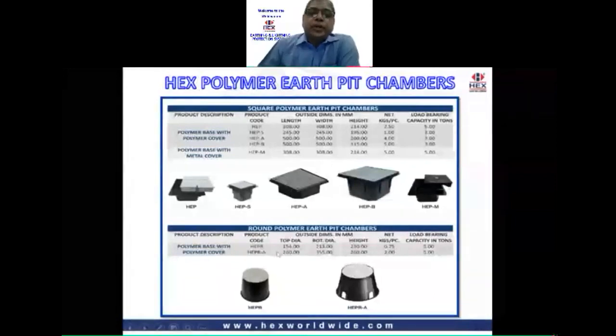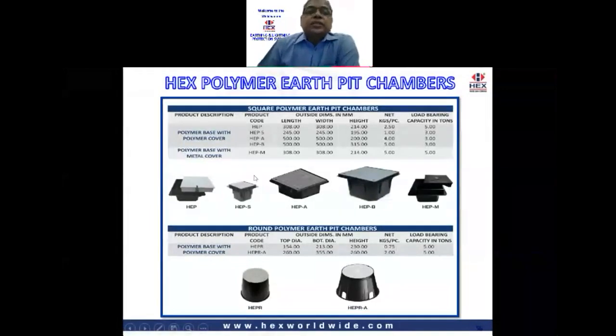Now, we have 5 sizes in square shape. Some with a nylon lid or a polymer lid, I would say, and some with a cast iron lid. HEPM is with a cast iron lid, metal cover. The smaller sizes, HEP, HEPS, and HEPM, have been tested for a load-bearing capacity of 5 tons, whereas HEPA and HEPB have passed a 3-ton load-bearing capacity. Both our round polymer earth pit chambers have been tested successfully for 5 tons.